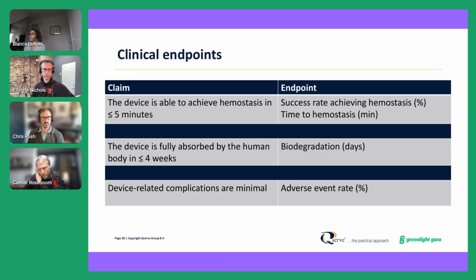Then the device is absorbed in the body in equal or less than 4 weeks. That's biodegradation. This is a difficult one in the clinical investigation because you need to do a biopsy to be able to do that. That's usually not something you can do in a patient if it's not part of the normal standard of care. Device-related complications are minimal. That's very simple. That's the adverse event rate of the most important individual adverse events. And what can we come up with more?